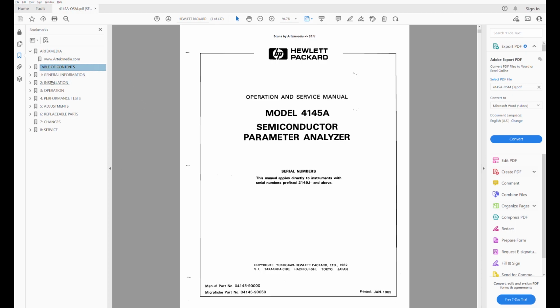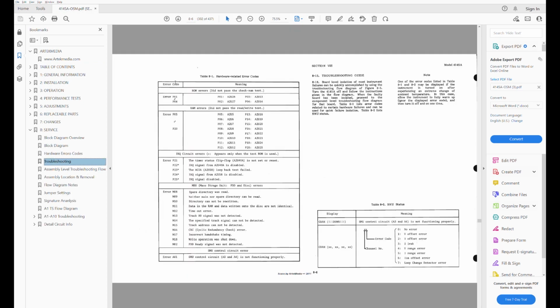Open Operating and Service Manual. Go to Section 8, Service. Open Section, Troubleshooting. Take a look at Table 8-1, Hardware-related error codes. We see at the bottom of the table the error code M02. It states, floppy disk drive signal was not detected.